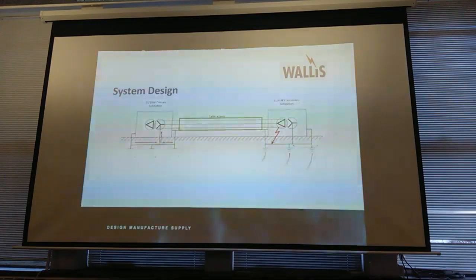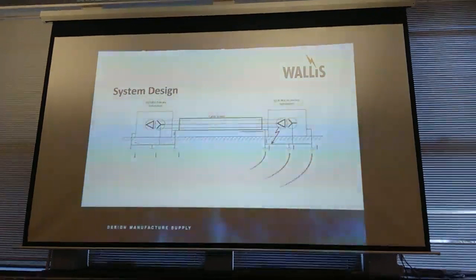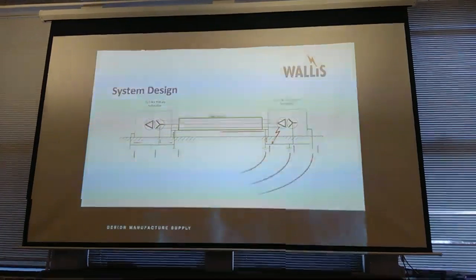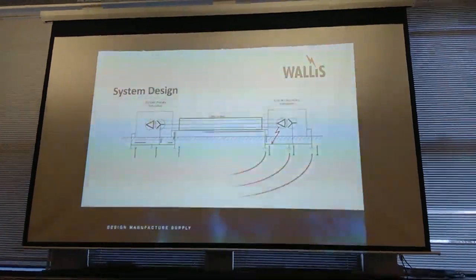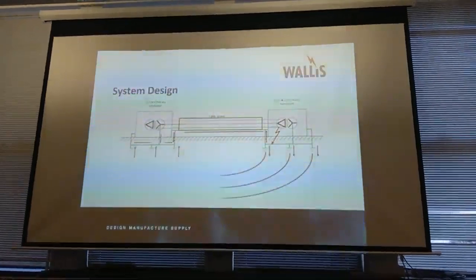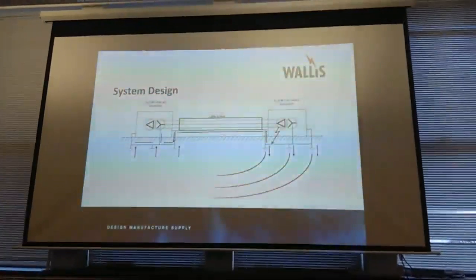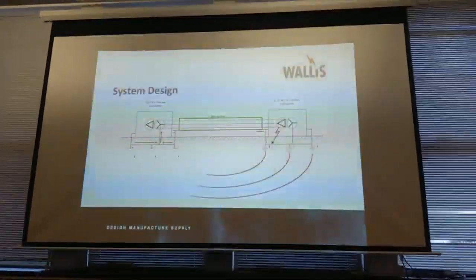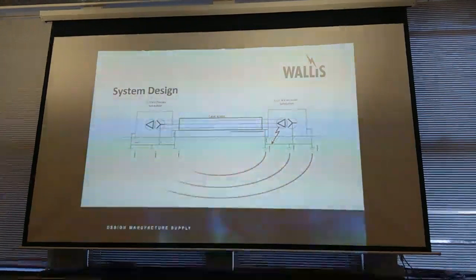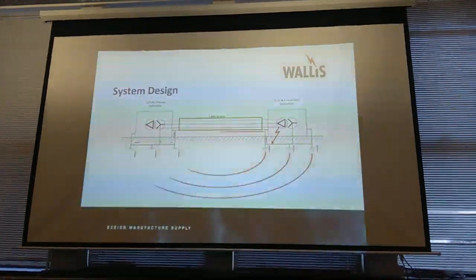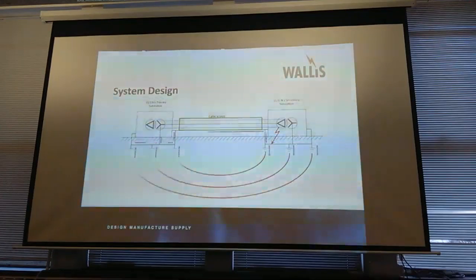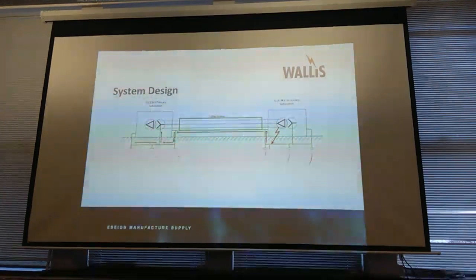Through the general mass of earth and back at the cable sheath. So that's your fault path. So again, it just shows that rather than looking at earth systems like that, your local substation, you have to look at the network as a whole. Because although you might have an earth system for that substation, and you might be putting earthing in there, you might have another substation here and another one and another one. They're all going to be linked. So you need to look at the network as a whole, if possible.